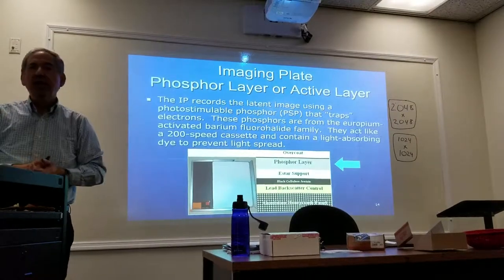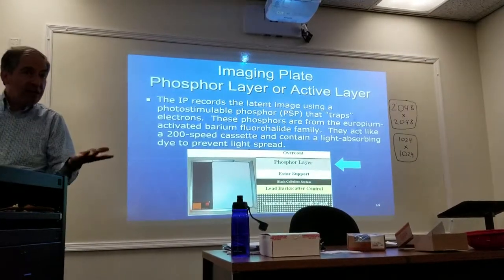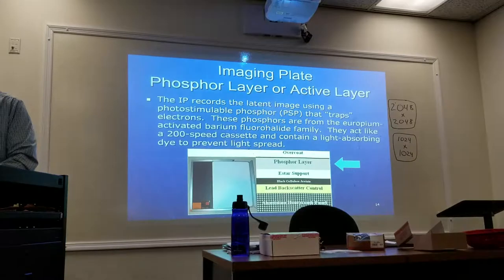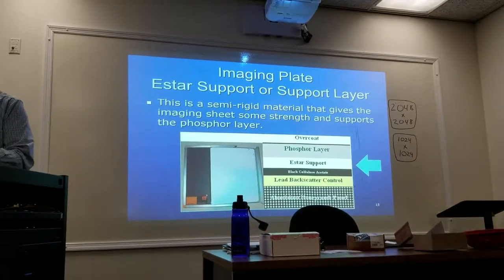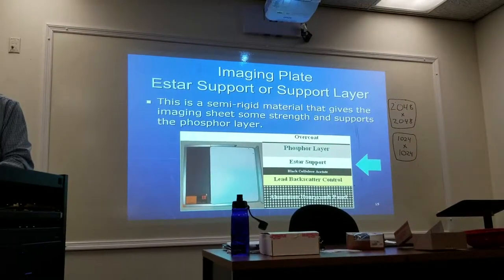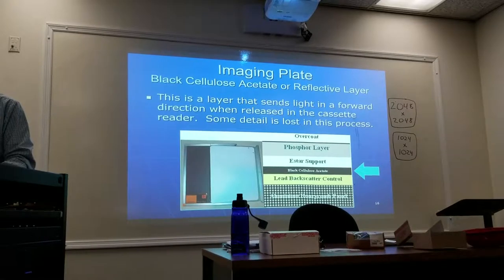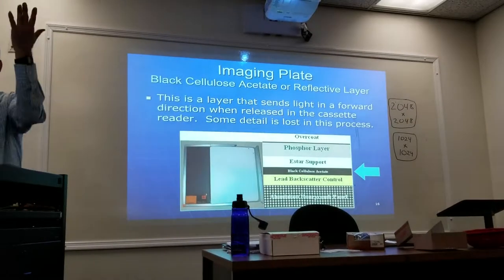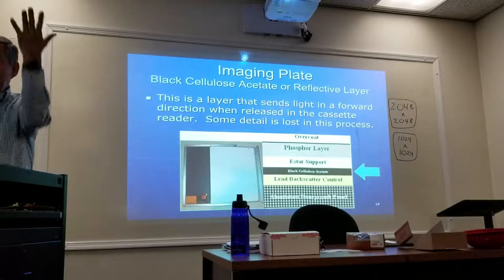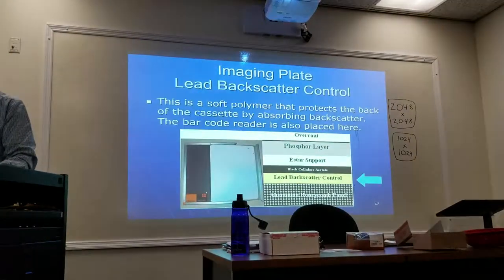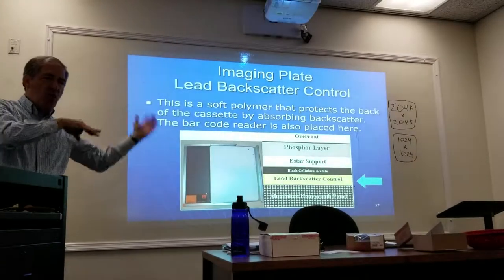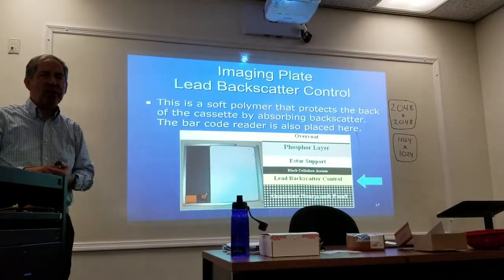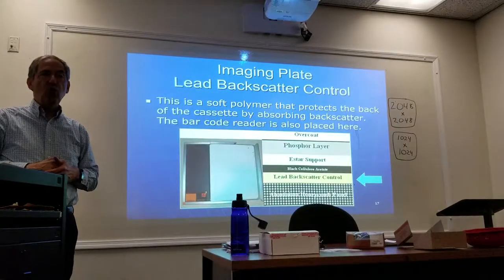The phosphors are made from what they call the europium-activated barium fluorohalide family. Europium as an activator is responsible for the ability to store energy — it causes the luminescence. It acts as a 200-speed cassette, which is a little slower but gives better detail. It also prevents light spread, keeping it confined. Then you have your support layer that gives support to the phosphor layer, and a black cellulose acetate layer that sends all the signals in a forward direction.